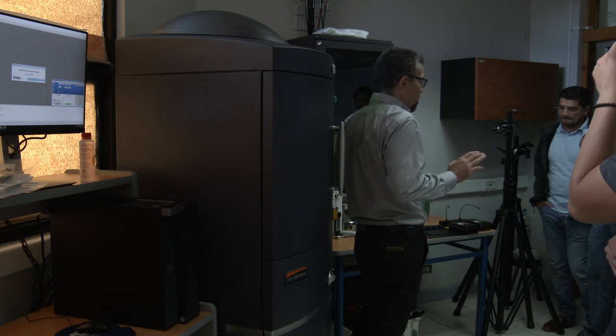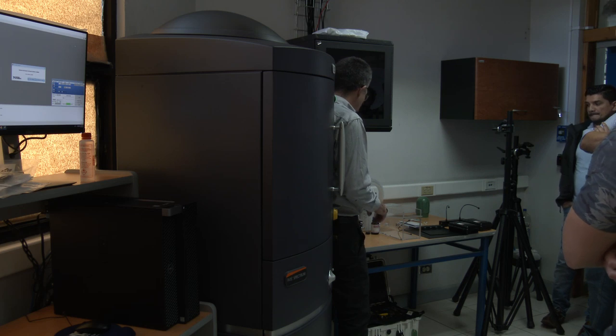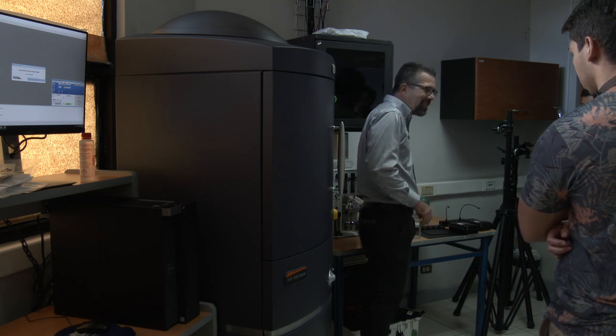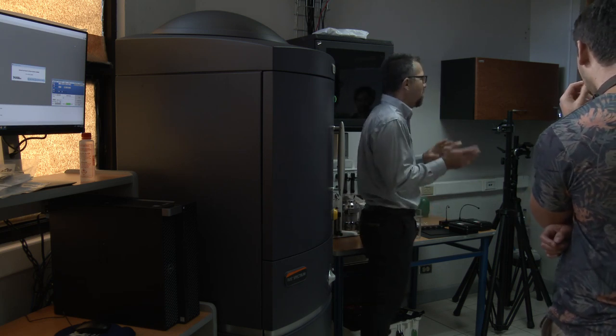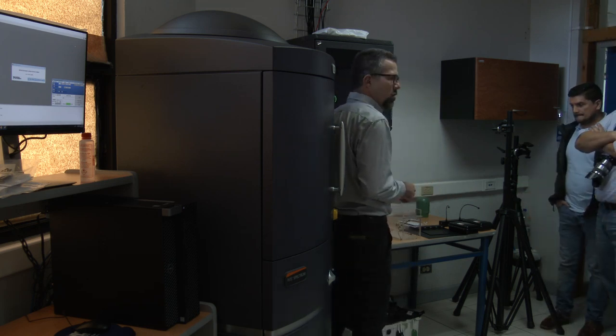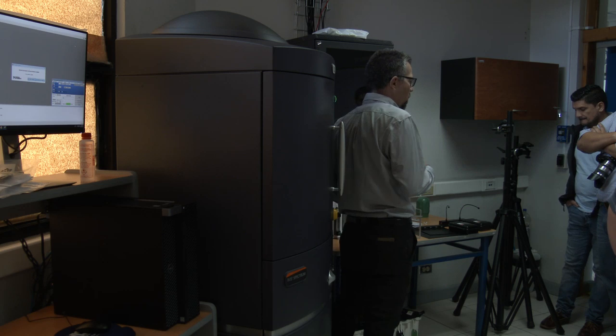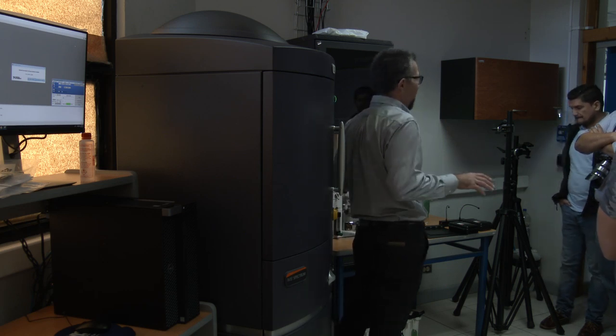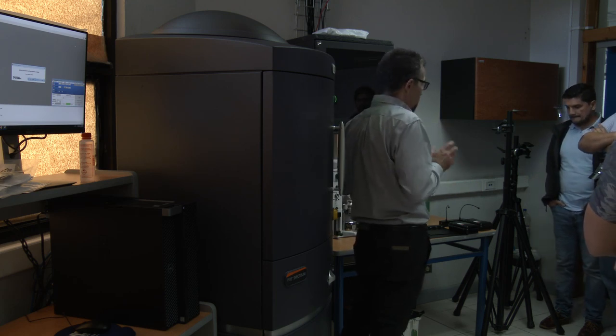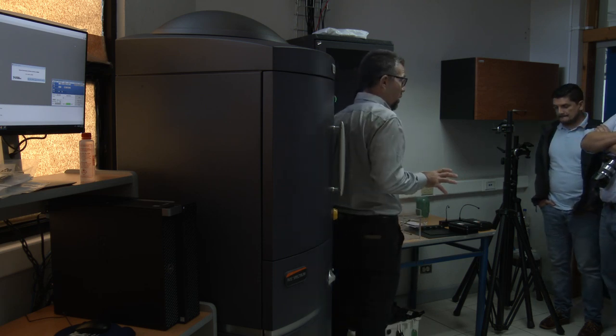Just two switches, okay? Oxygen is being supplied to the induction chamber at 1 liter a minute, and it's being vacuumed here at 10 liters a minute. So it's a nice 10-to-1 exchange ratio. Oxygen is being supplied to the IVIS at 500 cc's a minute, and it's being sucked out right here at 5 liters a minute. So it's a 10-to-1 exchange ratio. You should never smell isoflurane with this system. If you smell isoflurane, there's a problem. I don't know what the problem is, but there's a problem, right? Somewhere, something is disconnected. I don't know what it is.